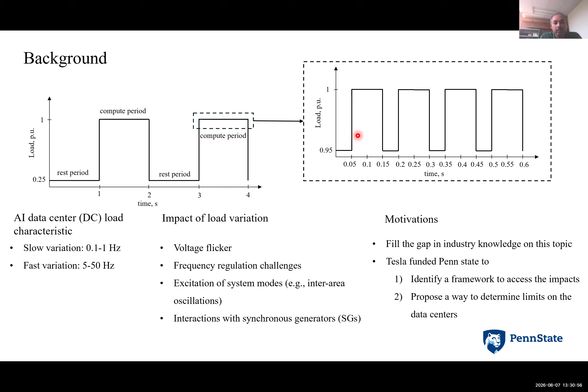The motivation is to fill the knowledge gap in industry so far as identifying a framework to assess the impact of such fluctuations on turbine generator shaft fatigue life is concerned. The other aspect we are looking into is how to come up with a limit imposed on these fluctuations from the utilities side, so that allowable fluctuations at the generator's terminals are respected, and as a result will not endanger shaft breakage or reduction of shaft fatigue life.